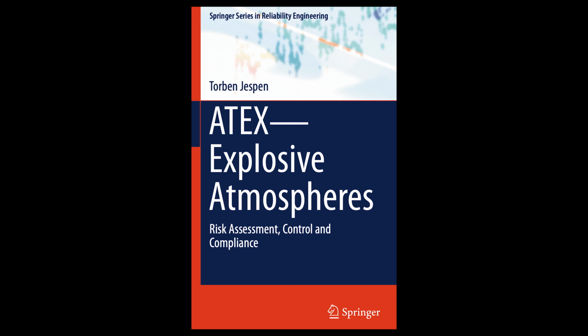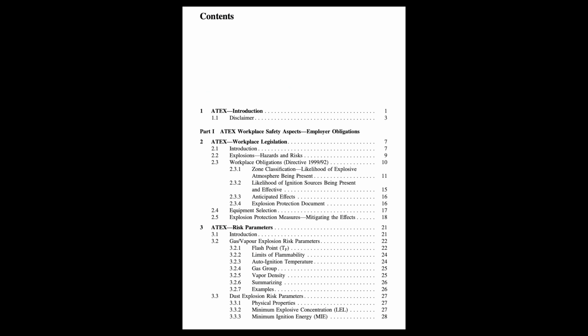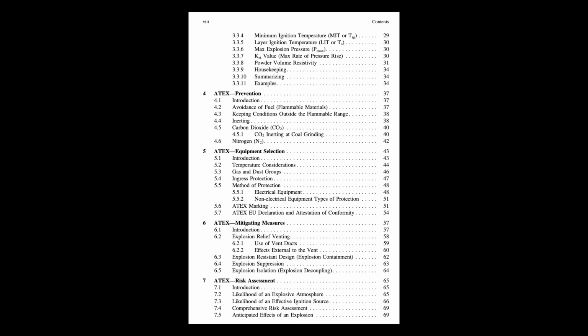Exactly. And this is really important because that smoldering layer can then act as a potent ignition source for a dust cloud if the dust gets disturbed. The LIT is typically measured for a 5 mm thick layer, and the guide notes that the dust's thermal history, if it's been heated before, can affect this value. So MIT for clouds, LIT for layers, both important. Both critical for setting maximum surface temperature limits for equipment used in dusty areas, again with safety margins applied.